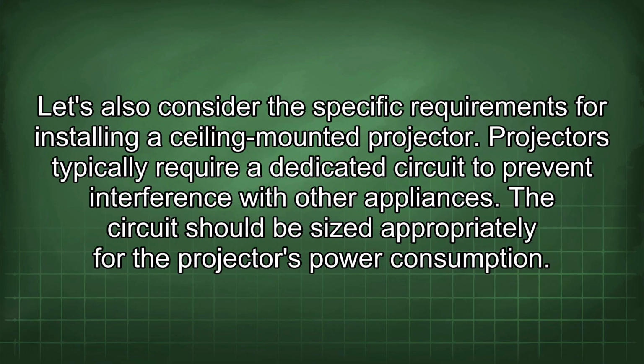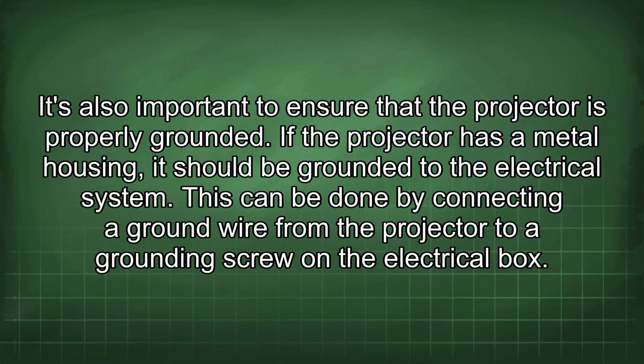Let's also consider the specific requirements for installing a ceiling-mounted projector. Projectors typically require a dedicated circuit to prevent interference with other appliances. The circuit should be sized appropriately for the projector's power consumption. It's also important to ensure that the projector is properly grounded. If the projector has a metal housing, it should be grounded to the electrical system. This can be done by connecting a ground wire from the projector to a grounding screw in the electrical box.